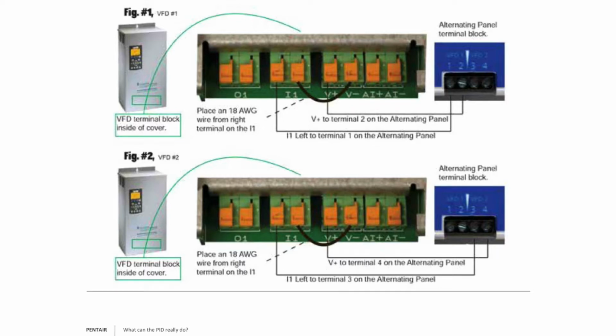But that being said, it's not a bad unit. It's a very good alternator. It's a simple device. And what we're doing here, as we show here, we are using the voltage off of our PID drive. So if you want to use a water sensor in conjunction with the alternator, it might be difficult to do so because we're taking that power supply away already.